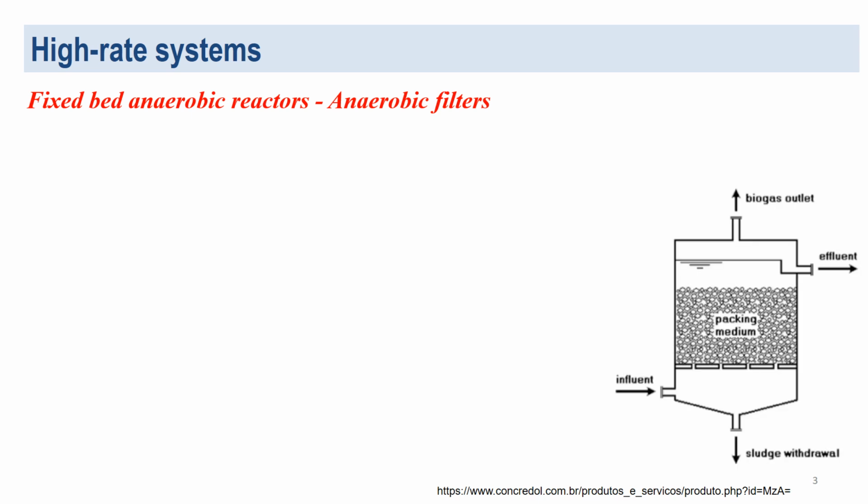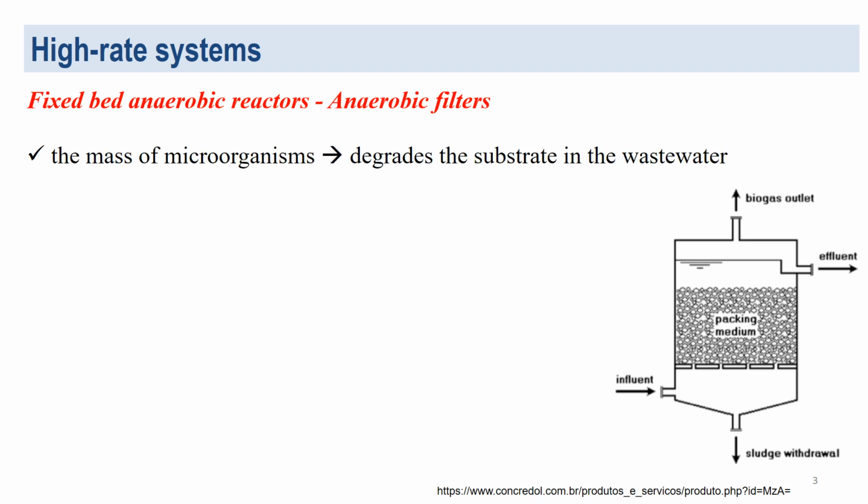A more commonly known example of reactors with attached bacterial growth in a fixed bed are anaerobic filters, as shown in the figure. These reactors are characterized by the presence of stationary packing material, where biological solids can either attach to it or be retained within the interstices. The mass of microorganisms attached to the support material or trapped in the voids degrades the substrate in the wastewater flow.